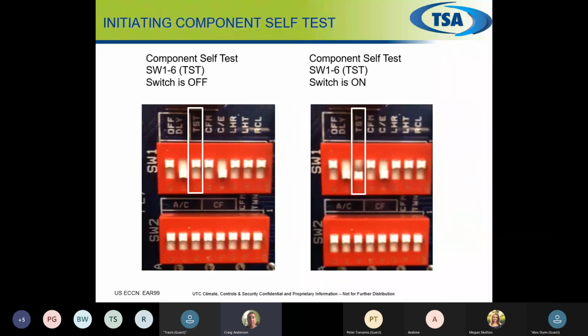So once we've verified all the power, we're good. We've got our constant voltage on our yellow, our brown, our power coming in. We're going back to our SW1-6 switch. We're turning it on. We want to see what this motor is going to do on our yellow wire. We know the brown's the feed in. We want to see what the yellow is going to do when that motor is supposed to start.